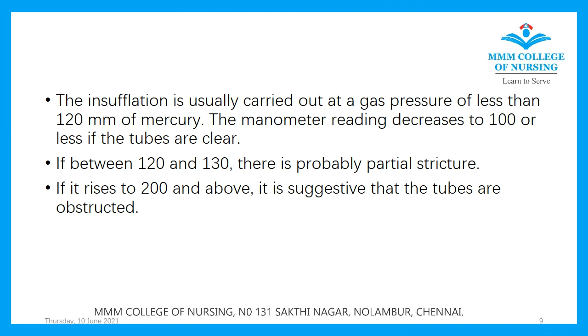So if the tubes are clear, the manometer reading or the pressure of the gas will be less than 100. If there is partial stricture, the manometer reading will be between 120 and 130. If the tubes are completely obstructed, the pressure will be rising to 200 and above. So this is about the Rubin's test. I think everyone has understood about this Rubin's test and the Rubin's cannula.